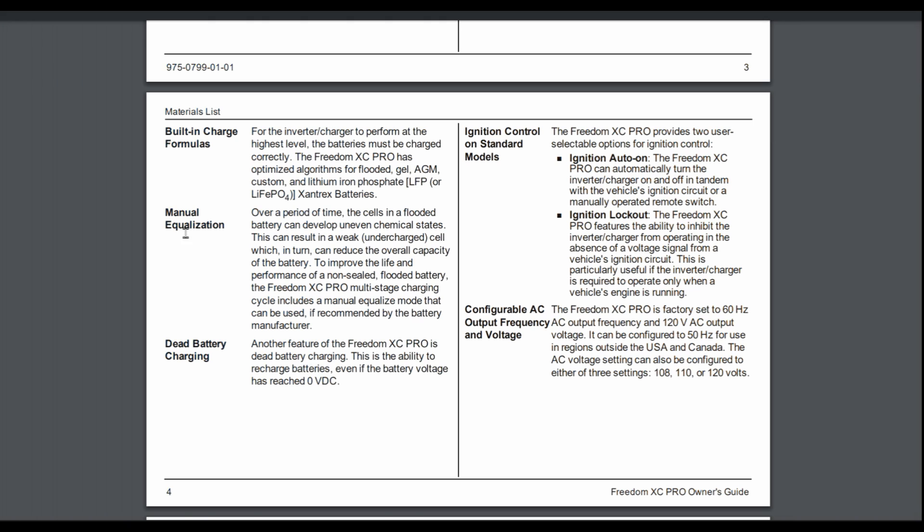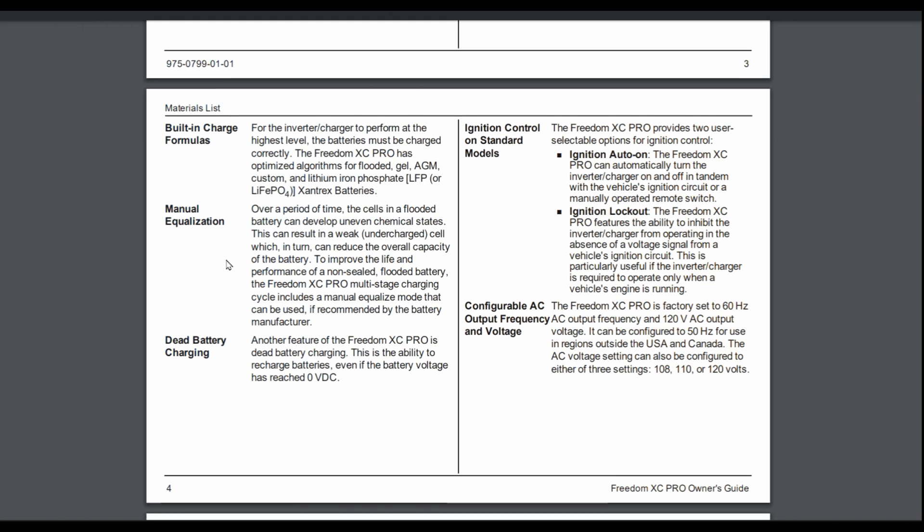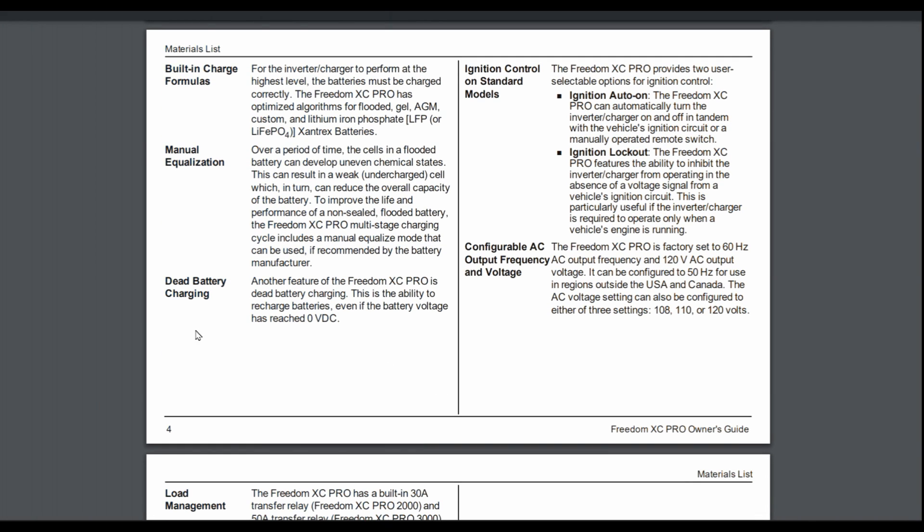Manual equalization. So this is for flooded-type batteries that sometimes they need to go through an equalization mode to desulfate their plates. So it's capable of doing that. A lot of chargers aren't capable of doing that. So that's a nice feature. And then something that's really handy for lithium is dead battery charging. Sometimes lithium batteries can get to a point where they go into a safety shutdown mode or they go actually into a sleep mode or they arrive in a sleep mode and basically they'll have zero volts on the terminal and you need a specialized type of charging unit to wake them up again. And this is capable of doing that as well.